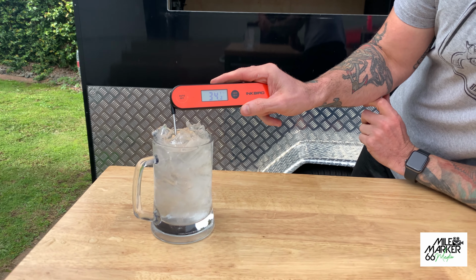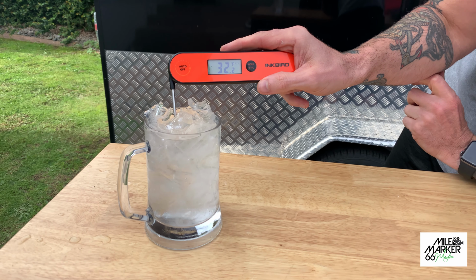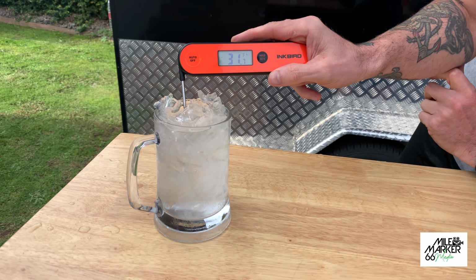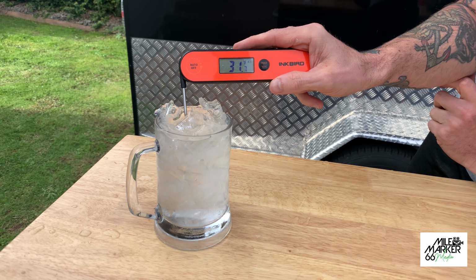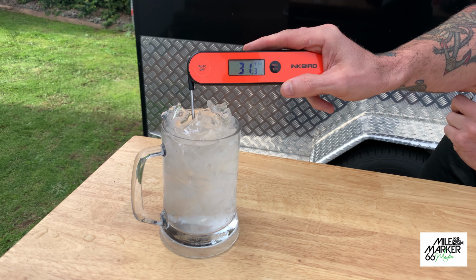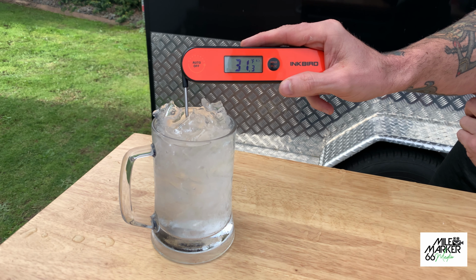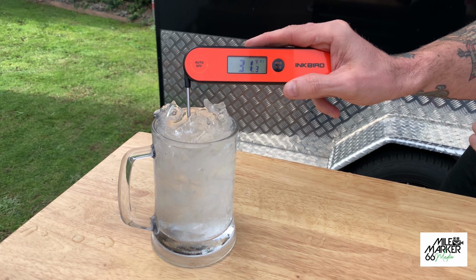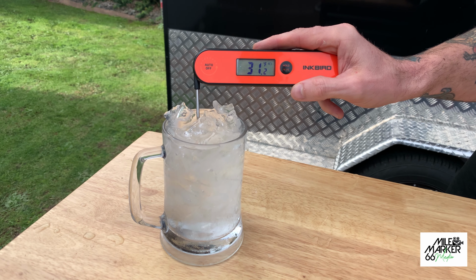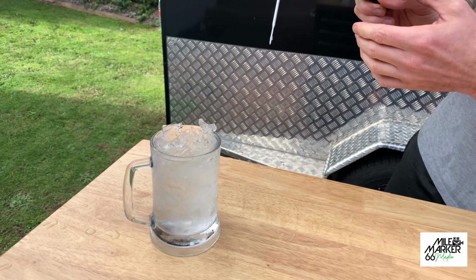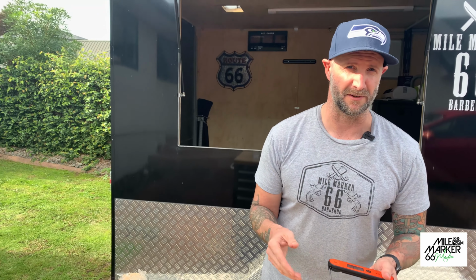Remember, we're looking for 32 degrees Fahrenheit. So, I mean, look at that. That's really pretty accurate. 31.7, and you're looking at points of a Fahrenheit degree. It's very little, but we'll go through the calibration procedure to show you. So we'll say that's settled out at 31.2, so we're under by 0.8 of a degree.